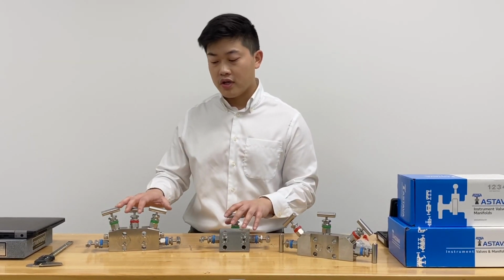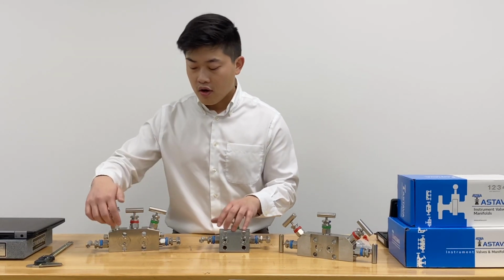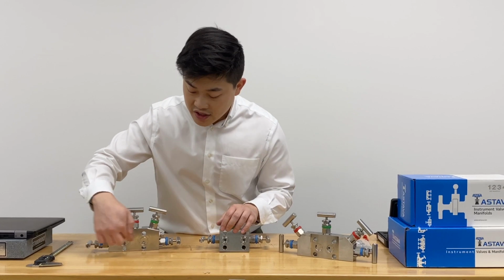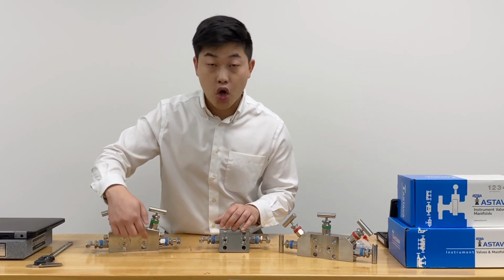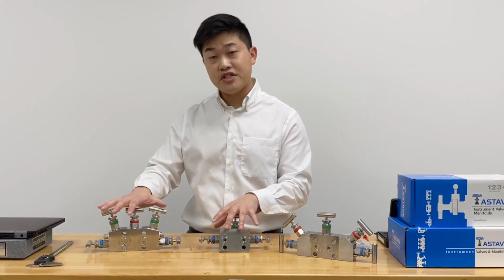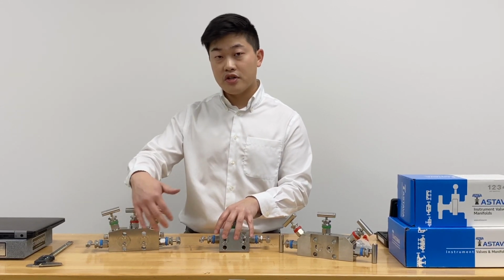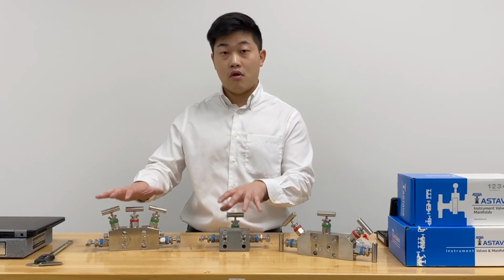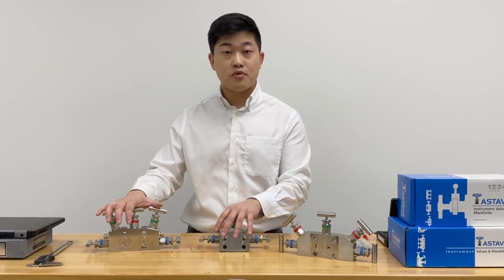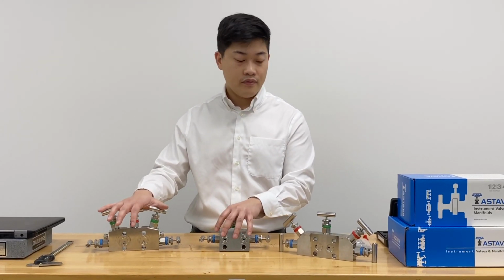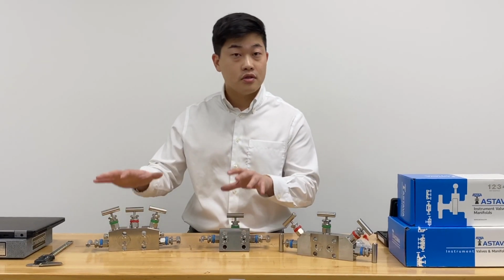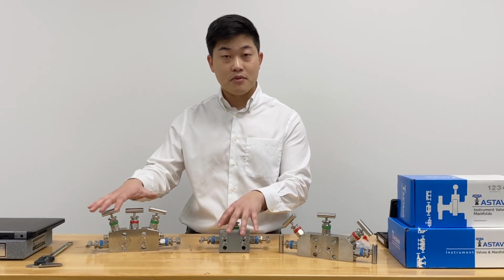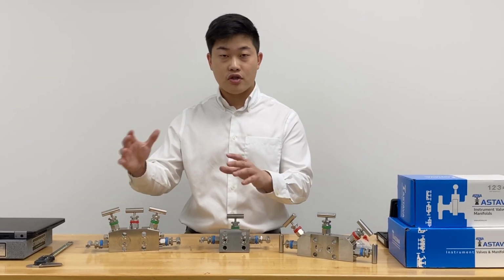What's important to know is that the similarities are that there's a 54 millimeter or 2 1/8 spacing center to center from the high and the low pressure ports. So these two right here have 54 millimeter center to center or 2 1/8. These two will mount to almost every single transmitter manufacturer you'd find out there. So that includes ABB, Yokogawa, Honeywell, Endress+Hauser, Siemens, Foxboro, etc., etc.